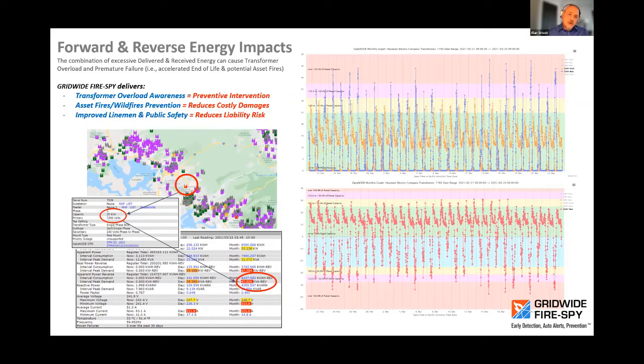The purple icons show instances where reverse energy was detected at each transformer point over the last 24 hours. Yellow or red icons indicate reverse energy instances that exceeded the transformer's capacity or nameplate rating, with red typically indicating a substantial overload situation. In this case, a 25 kVA transformer is actually handling over 47.5 kVA of reverse energy—that should catch someone's attention.